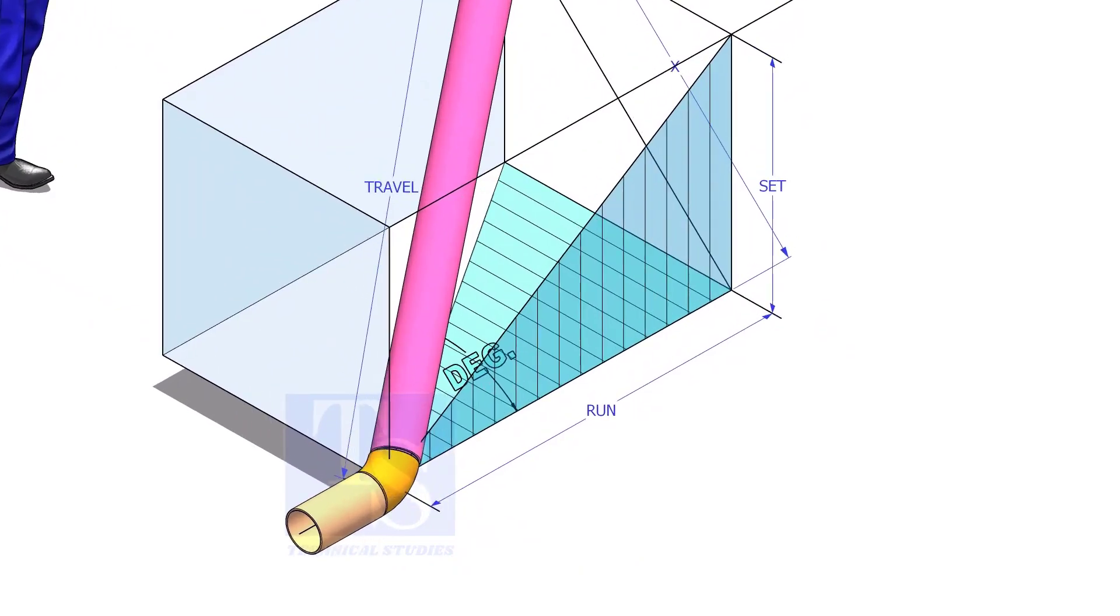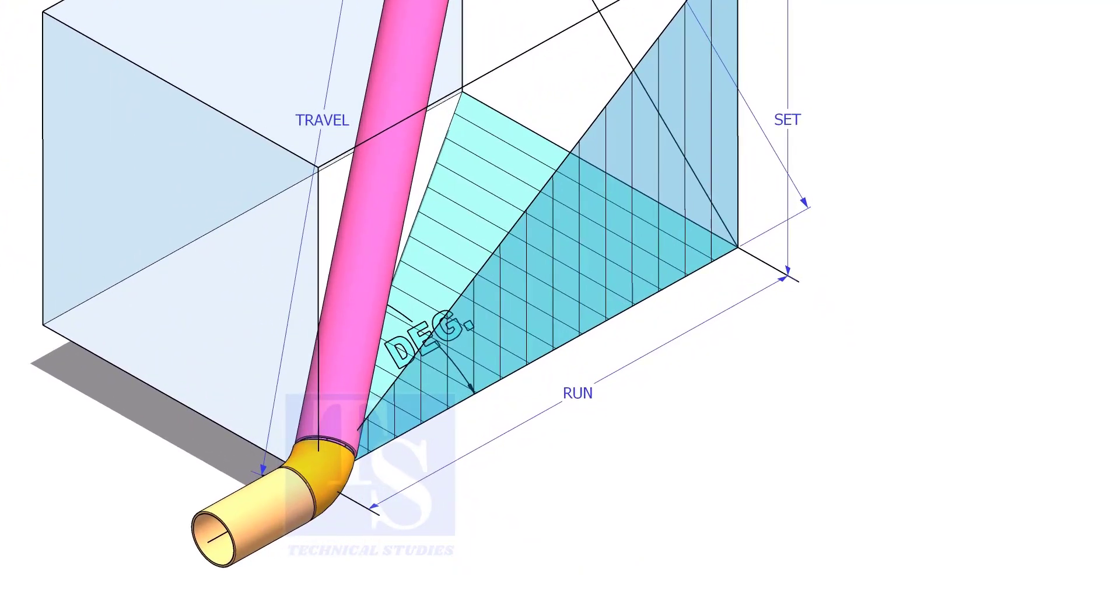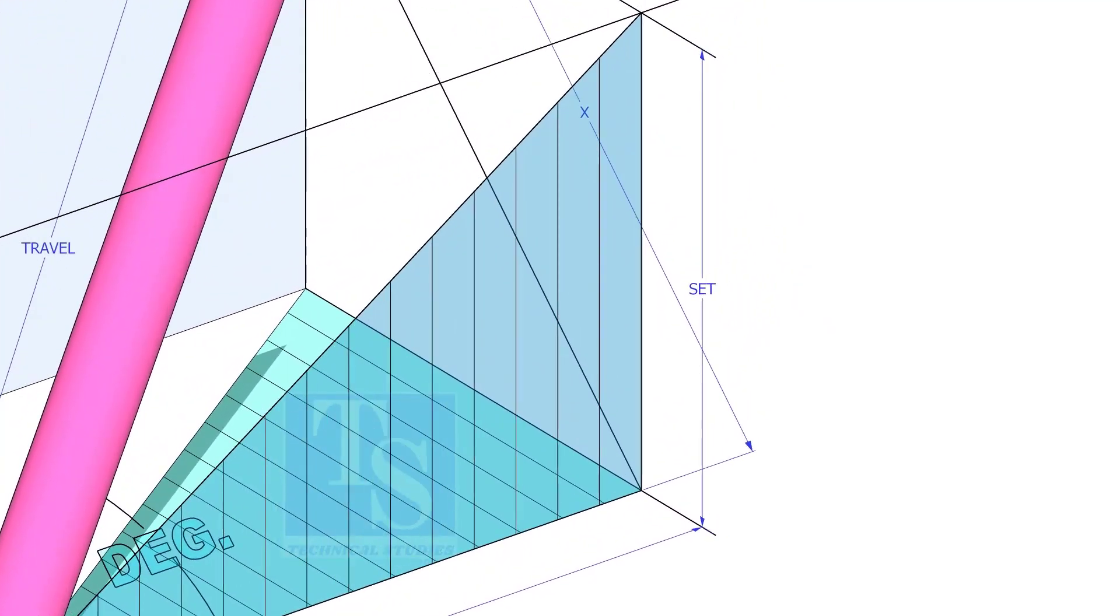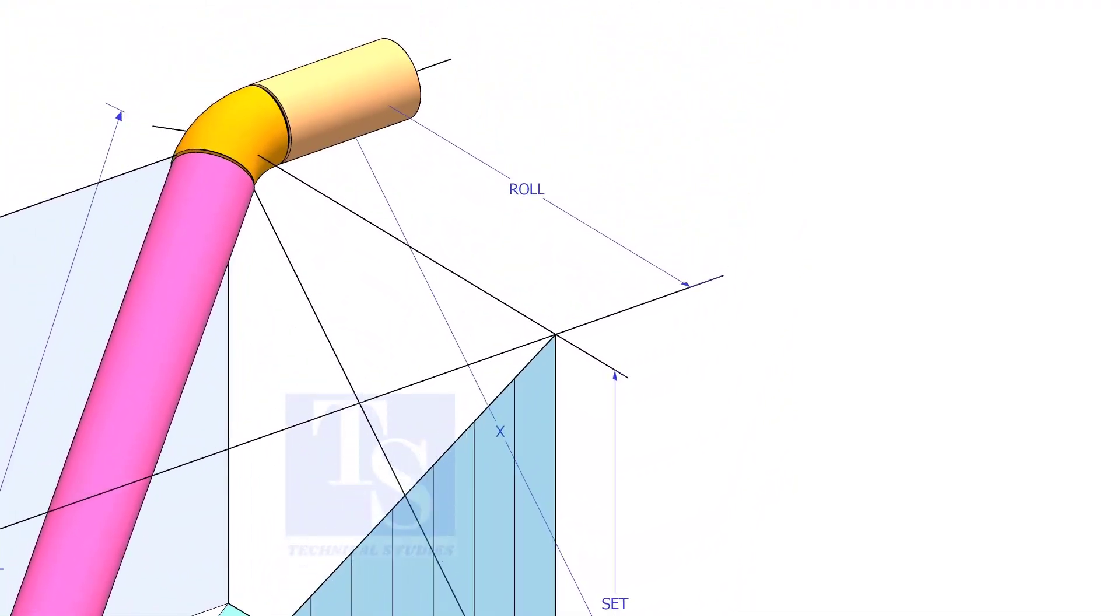In this video, I will show you how to calculate the travel length and the including angle of a double rolled offset pipe.